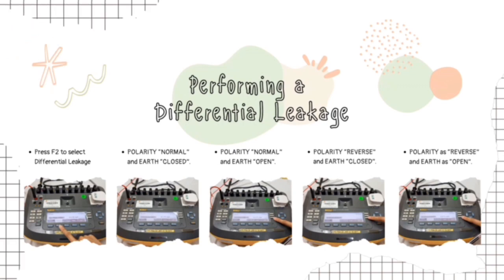Next is performing a differential leakage. First, press F2 to select differential leakage. Choose polarity normal and earth closed, and then choose the polarity normal and earth open, and polarity reverse and earth closed, and choose the polarity as reverse and earth as open. Like usual, after choosing the polarity and earth, we must press test for the result.